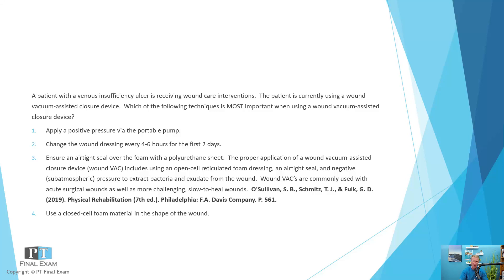This is what would be considered sub-atmospheric pressure — it is a vacuum that's trying to slurp all of the exudate out of the wound. There are even some devices that cycle by pumping a saline solution to irrigate the wound and then suck it back out again, which helps remove bacteria and prevent colonization. Proper application of a wound VAC includes using an open cell reticulated foam — open cell meaning fluid can travel between the cells, as opposed to closed cell where fluid cannot communicate from bottom to top or side to side. You need that open cell reticulated foam dressing so that exudate can travel through the foam, along with an airtight seal and negative sub-atmospheric pressure.